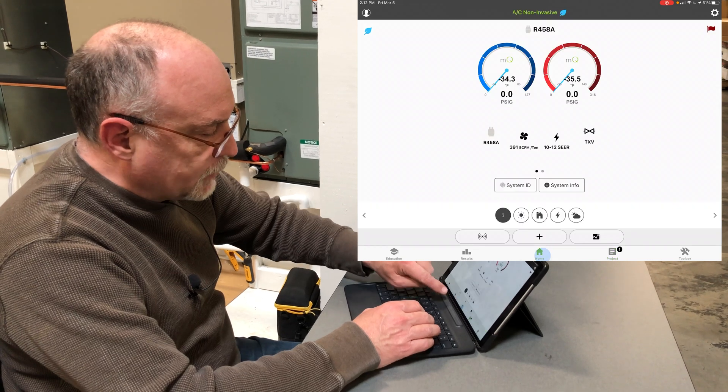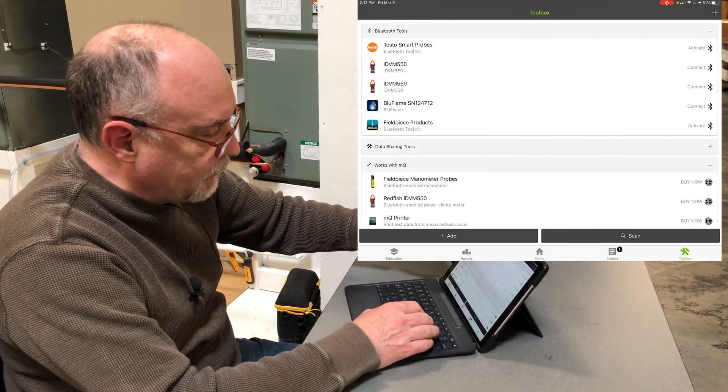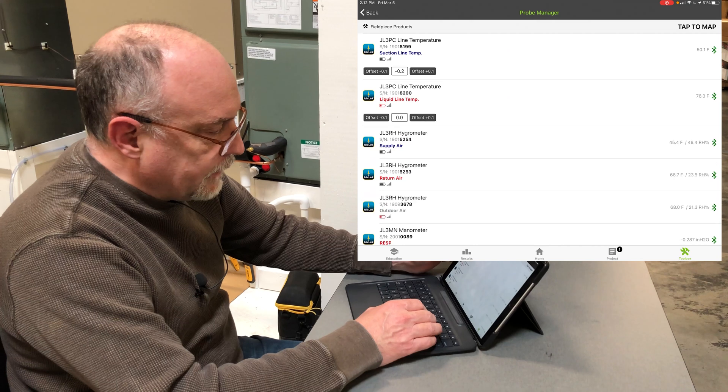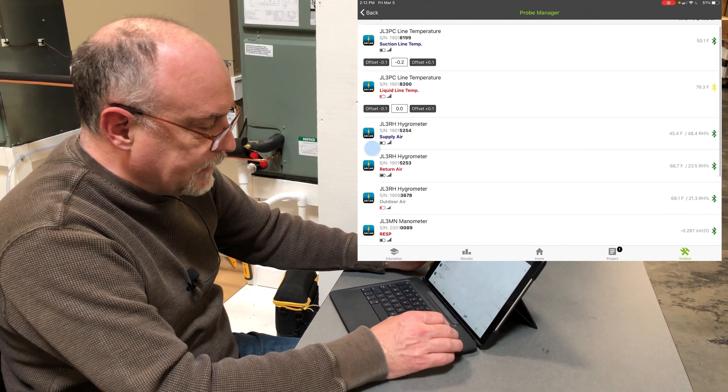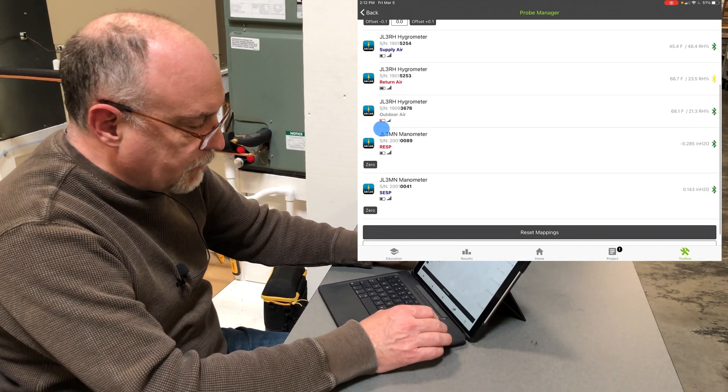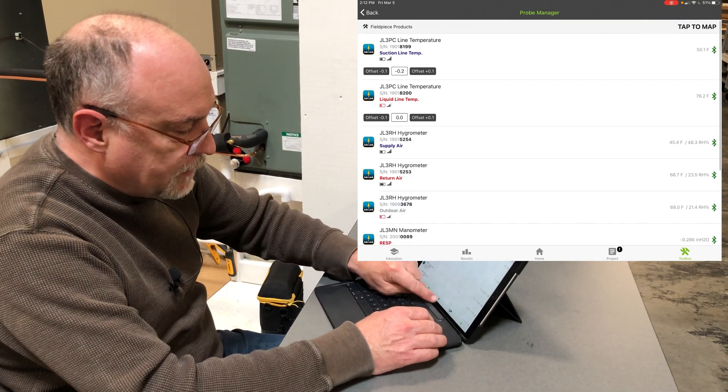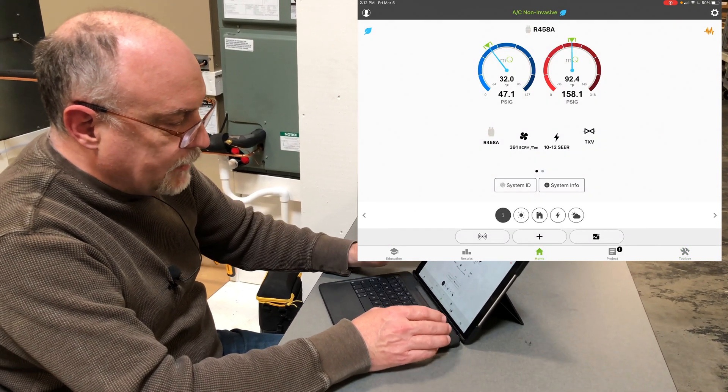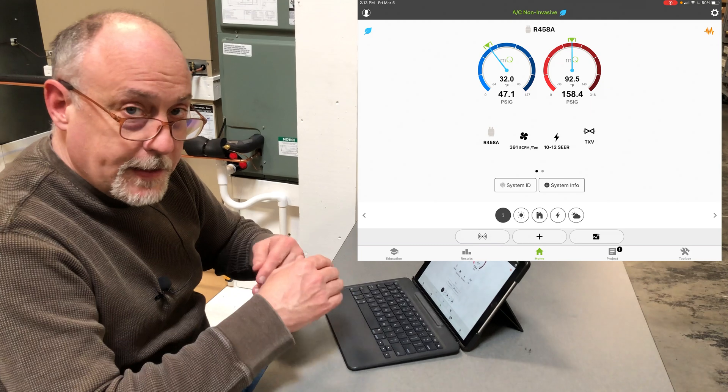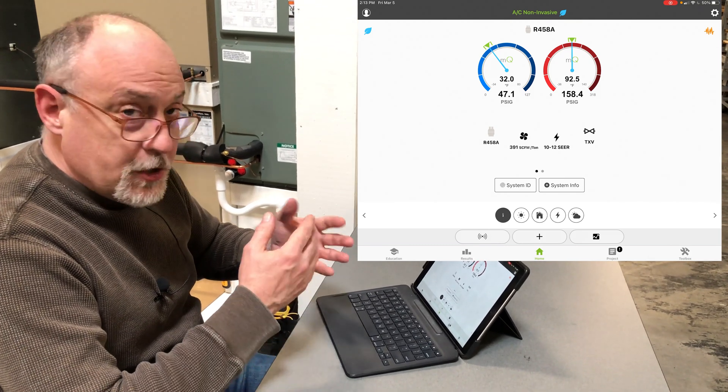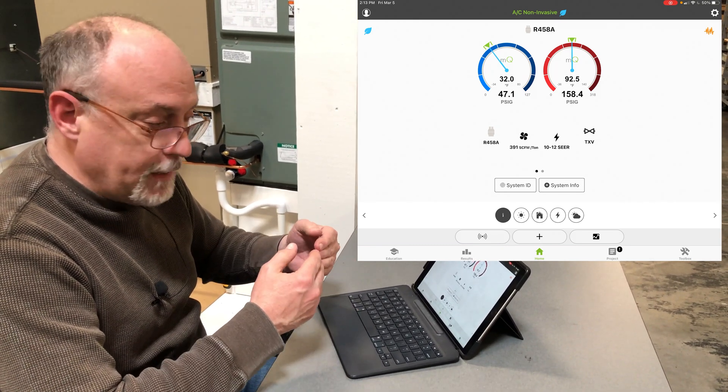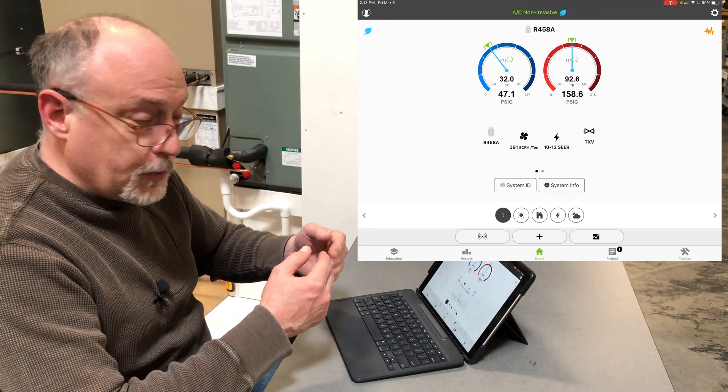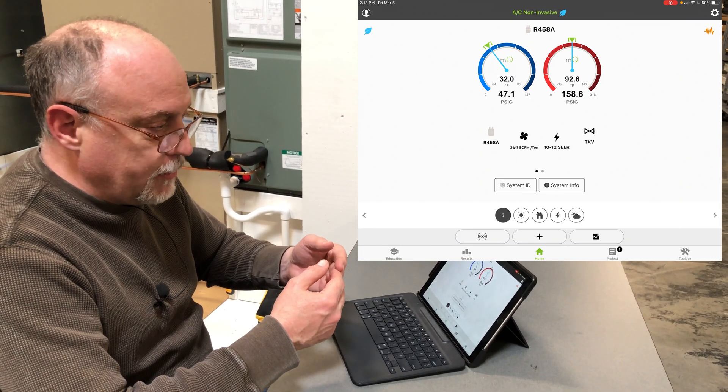It's asking me now to take measurements. I'm going to go to my home screen and activate my probes. In my probe manager I have a suction line and liquid line, supply air, return air, outdoor air, return and supply statics, but no pressure probes. When I go to the home screen, you're going to see I have blue needles right now. The blue needles signify what the pressures would be if we were actually measuring them. Those are driven by the outdoor air temperature and the return air temperature and humidity.